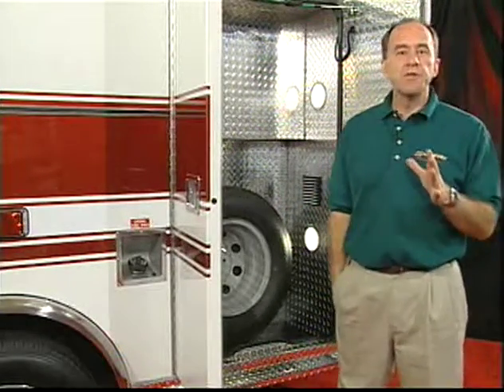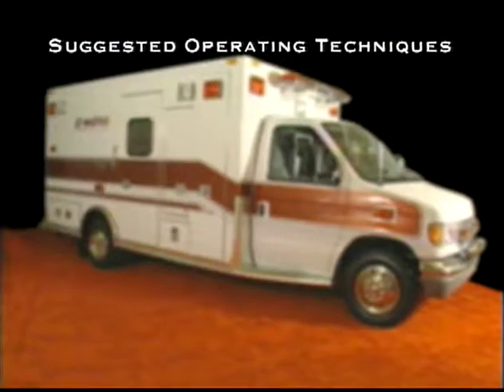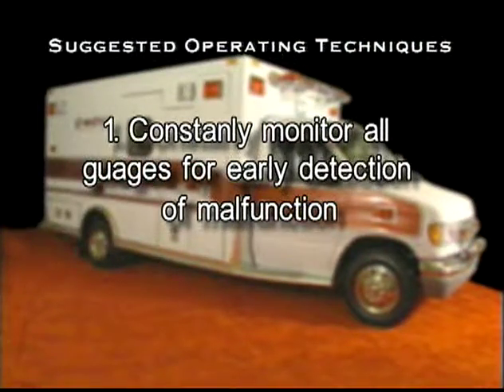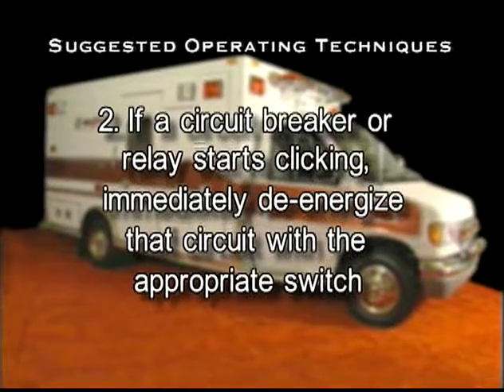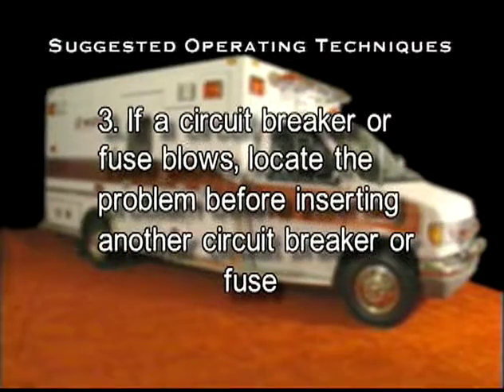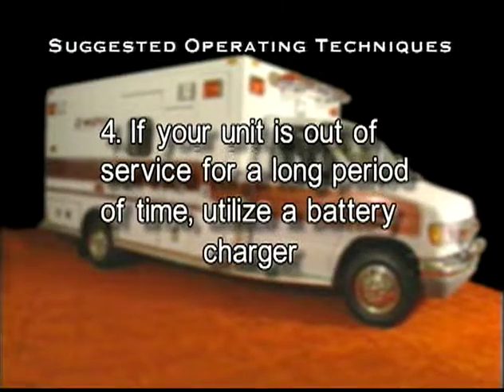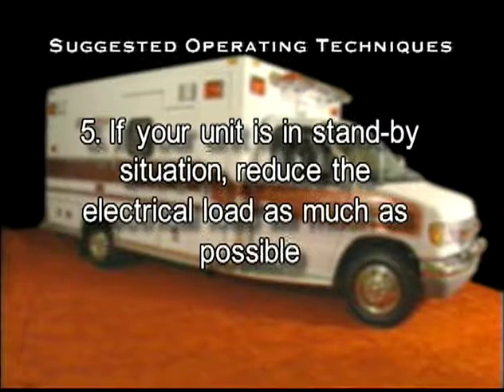The following is a list of some suggested operating techniques. 1. Constantly monitor all gauges for early detection of malfunction. 2. If a circuit breaker or relay starts clicking, immediately de-energize that circuit with the appropriate switch. 3. If a circuit breaker or fuse blows, locate the problem before inserting another circuit breaker or fuse. 4. If your unit is out of service for a long period of time, utilize a battery charger. 5. If your unit is in a standby situation, reduce the electrical load as much as possible.